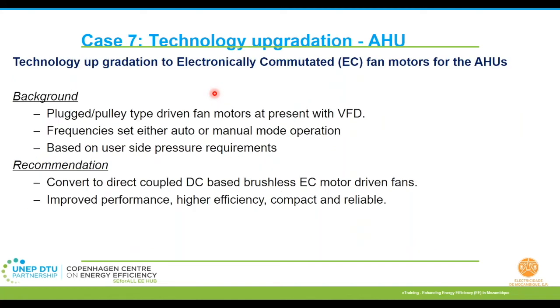Technology upgradation for air handling units. Most of you will have seen air handling units either in malls or large office spaces. These types of AHUs often have fans which are either plug type or pulley type driven motors. They may or may not have variable frequency drives in place. And even if they have, the frequencies would either be set in auto or manual mode, completely based on the user side pressure requirements. So we have come across this latest technology. It's not the latest actually. It's been around for at least 4 to 5 years now.